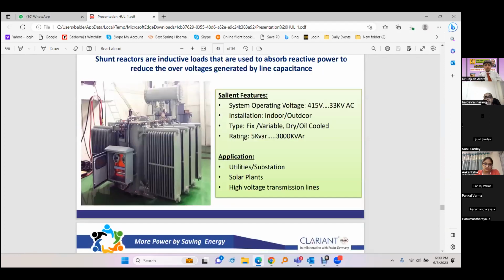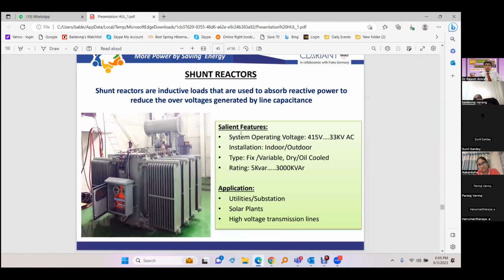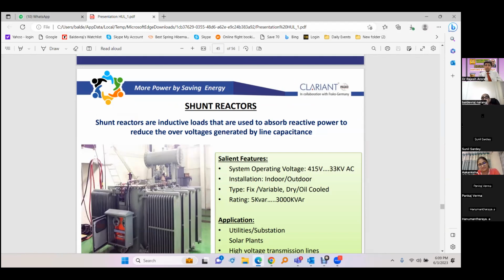This is a very recent requirement. Shunt reactors: we have given them to HPCL Mittal Energy. They have a plant where the line is about 11 kilometers long, and when they take a shutdown, the power factor is highly leading. The line capacitance is about 1200 kVAR, and the power factor goes to 0.1, 0.2 leading, and they have a heavy penalty. They used to pay penalties in crores of rupees because shutdowns are very common. Every month they have 1 or 2 shutdowns sometimes, and during Corona it was almost a continuous shutdown. So they lost a very heavy amount because of these penalties.